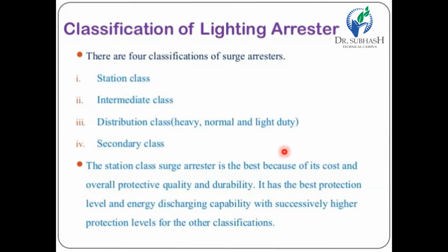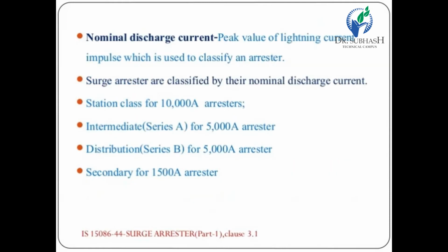Classification of lightning arrestors. There are four classifications of surge arresters: station class, intermediate class, distribution class, and secondary class. The station class surge arrestor is the best because of its cost and overall protective quality and durability. It has the best protection level and energy discharging capability, with successively higher protection levels for the other classes.